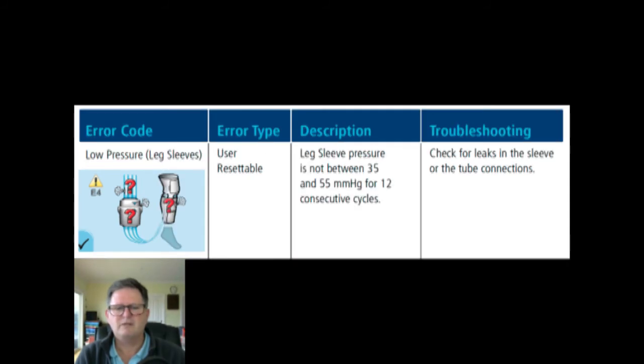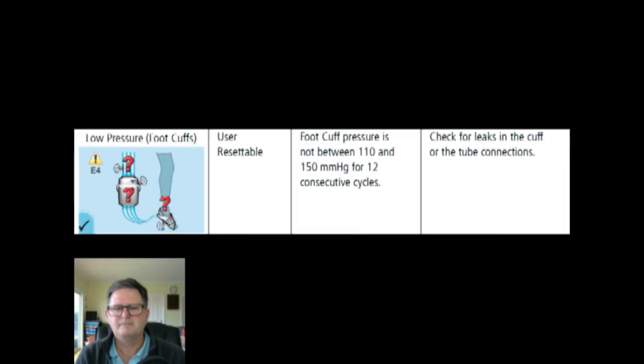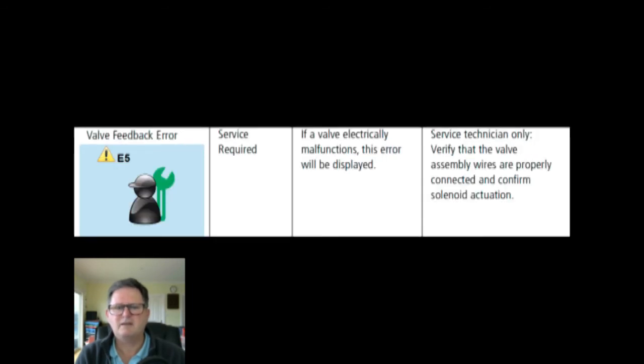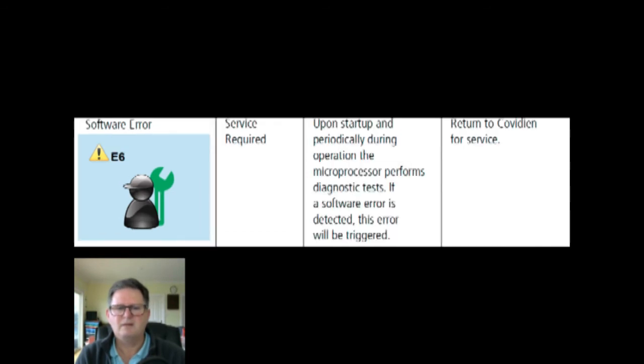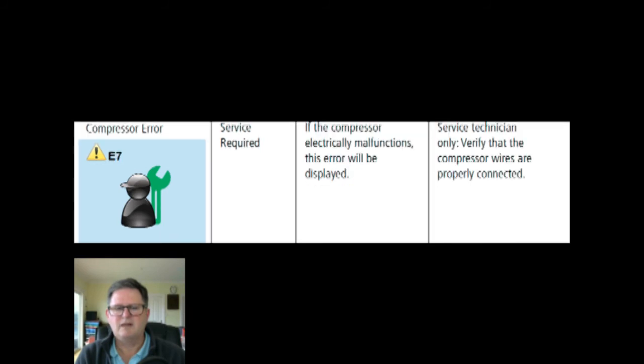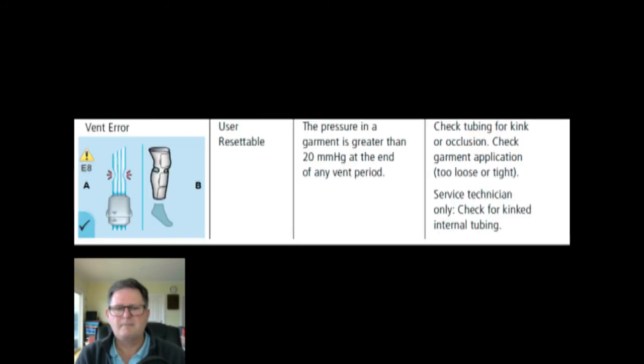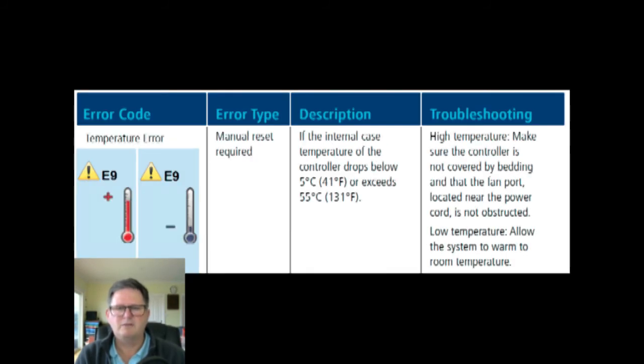So mostly user sort of things, like lack of pressure or too much, so a hose might be kinked or something like that. And then there are real errors to do with the actual hardware. Again, they don't tell you much, you've got no idea what to really do, but typically the pump fails, or some sort of valve is stuck, maybe the battery's faulty, or it's out of temperature for whatever reason.